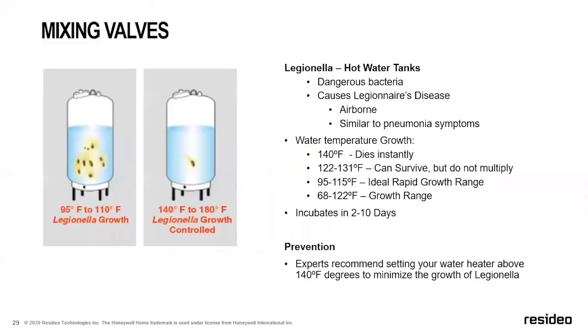One of them is we can increase the temperature of our tank. So if we're running right around 110 degrees, you can see that there's more potential for Legionella growth. As we start cooking that water higher in our tank, we can restrict the growth of Legionella, right? So the higher you go, the less Legionella, as you can see with the water temperature growth. At 140, it dies instantly. Between 122 and 131 degrees, it can survive, but does not multiply. That range of 95 to 115, I see a lot of water heaters set at, and that's the ideal rapid growth range of Legionella. So higher the better; it can't survive.